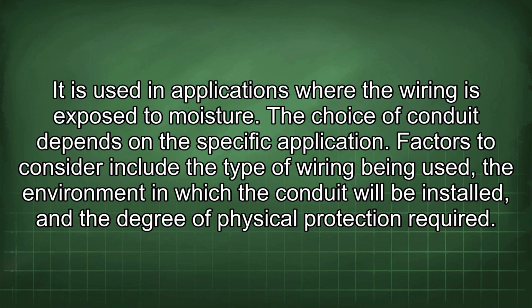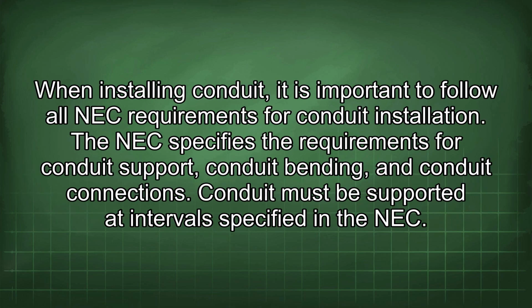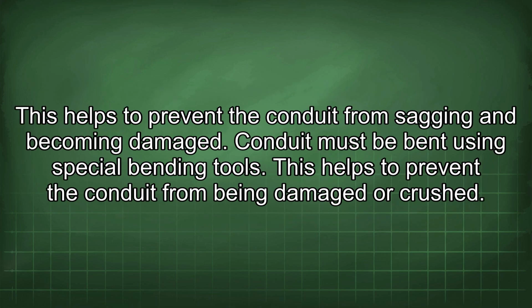The choice of conduit depends on the specific application. Factors to consider include the type of wiring being used, the environment in which the conduit will be installed, and the degree of physical protection required. When installing conduit, it is important to follow all NEC requirements for conduit installation. The NEC specifies the requirements for conduit support, conduit bending, and conduit connections. Conduit must be supported at intervals specified in the NEC. This helps to prevent the conduit from sagging and becoming damaged.